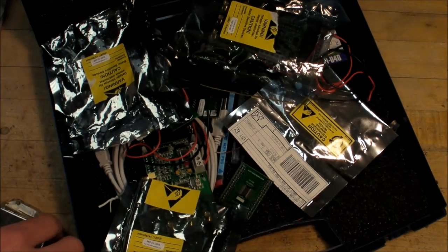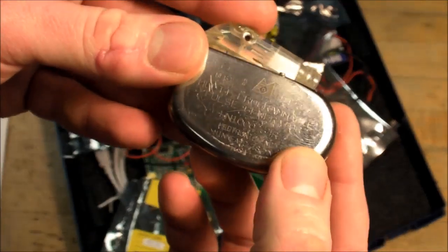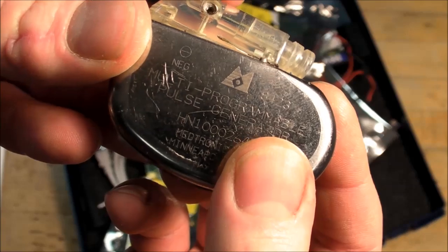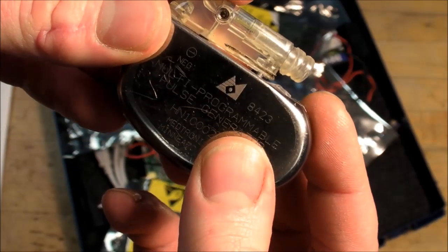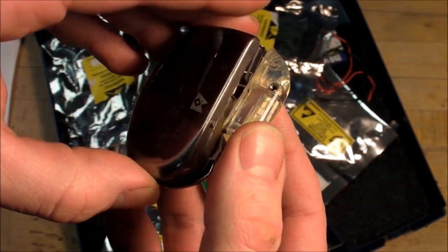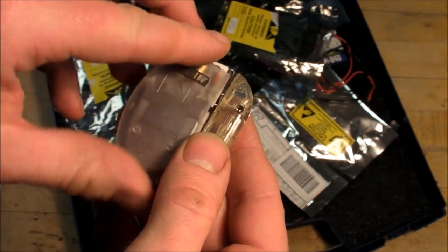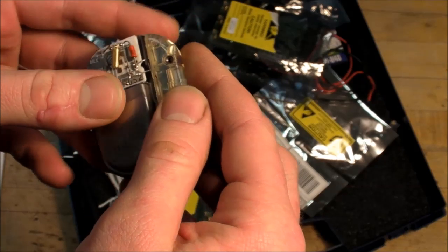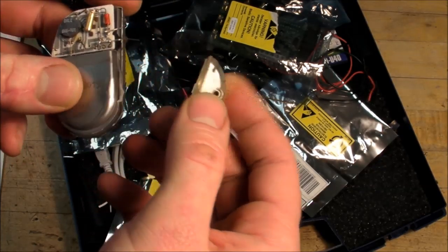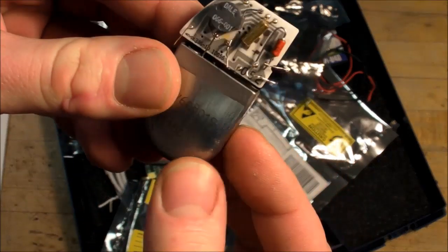This one, you can see the date code here, 23rd week of 1984. So I'm not sure if this actually had any communication possibilities because the technology in here is much simpler than the defibrillator that Mike took apart. But basically it really only just has one single connection going out to the heart, just one single wire to create the pulse for the heart.